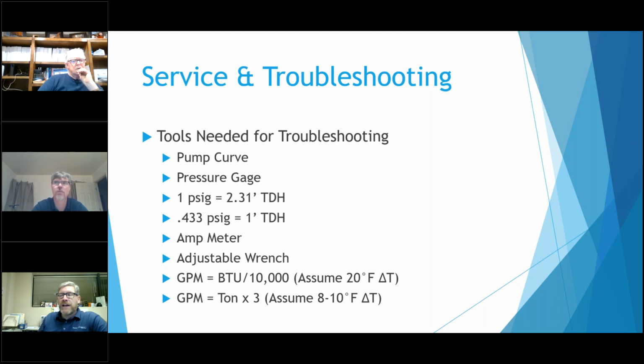Having a good ammeter is nice because that way we can check the amp draw that the motor has. An adjustable wrench seems kind of interesting, but you want one, because once you get past the smaller triple duty valves and circuit setters, they all have a flat to them, or a square in the case of the triple duty valves and big circuit setters. The only way to really open and close those is with an adjustable wrench. So it's good to have a pretty good sized wrench around. Sometimes they're hard to open and close.